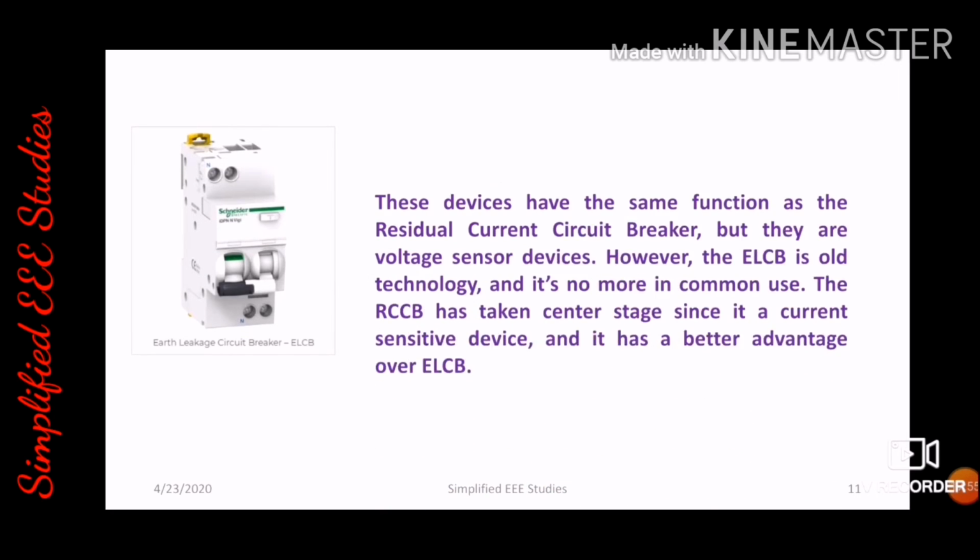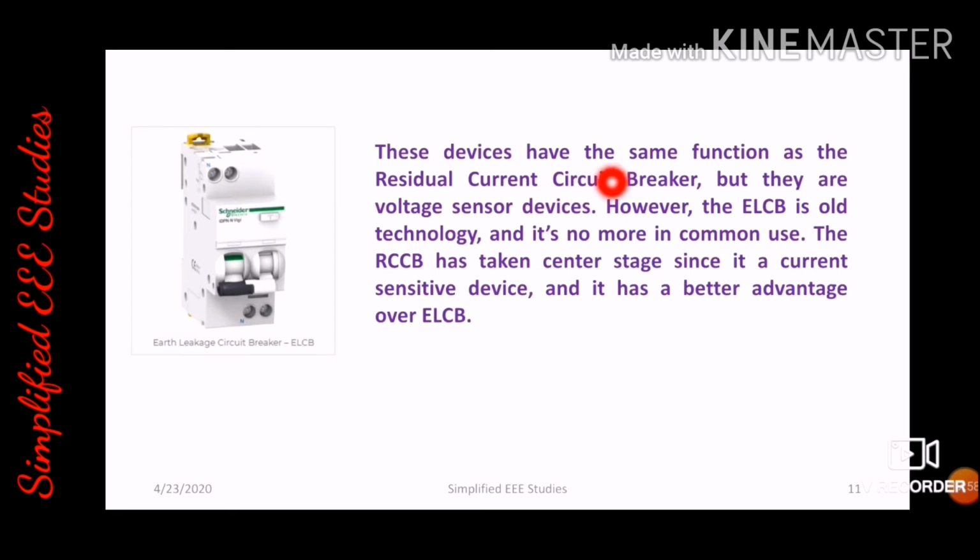The comparison between RCCB and ELCB has been given in the next slide. As you can see, the diagram of the earth leakage circuit breaker. These devices have the same function as the residual current circuit breaker. Then what is the difference? They are voltage sensor devices. However, the ELCB is old technology and it's no more in common use. The RCCB has taken center stage since it's a current sensitive device and it has better advantage over ELCB.